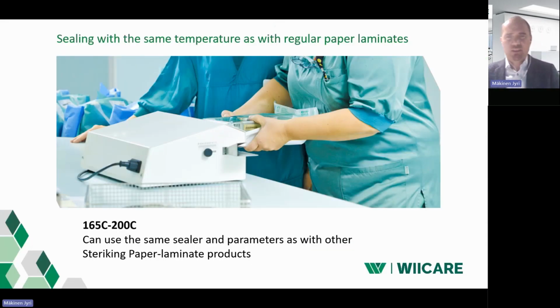Once you have the right size piece for your instrument, you seal it with the sealing machine. Great news here — you can use the same sealer and sealing parameters as with other paper laminate products, so you don't need a separate sealer. You can use temperatures from 165 to 200 degrees, and this has been tested for the worst case scenario at 165, confirming it still creates the seal.